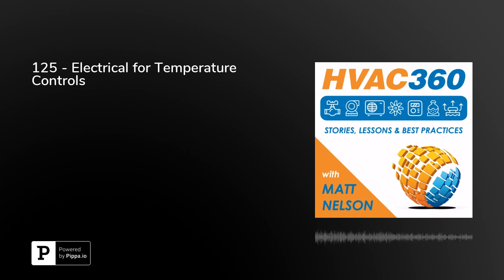What else are you going to use outside of the temperature controls panel? Well, typically there are going to be transformers. There may be transformers out in the space. Transformers could feed VAV boxes. If you have VAV boxes that require power, they might be linked to a common transformer. Your transformer is going to be limited by the number of devices it can serve. That's where you want to coordinate the locations of your boxes with your electrician or your electrical engineering counterpart to make sure that their design is going to be adequate for what you're trying to do.